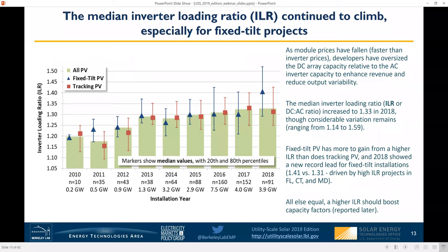The final technology aspect I want to highlight before turning to pricing is the inverter loading ratio, or ILR, which measures the DC capacity of the PV array relative to the AC capacity of the inverter — also known as the DC to AC ratio. The median ILR has increased pretty steadily from around 1.2 in the early days of the market to above 1.3 in 2018. This progressive oversizing of the PV array optimizes inverter throughput as the cost of modules has declined faster than the cost of inverters. Oversizing can lead to some clipping at midday, but that is more than offset by increased production during morning and evening shoulder periods, leading to a net increase in AC capacity factor.